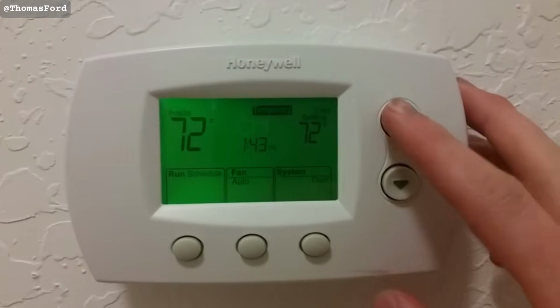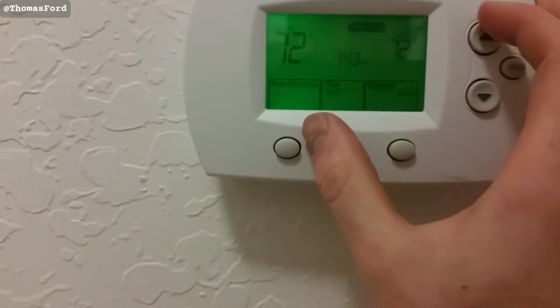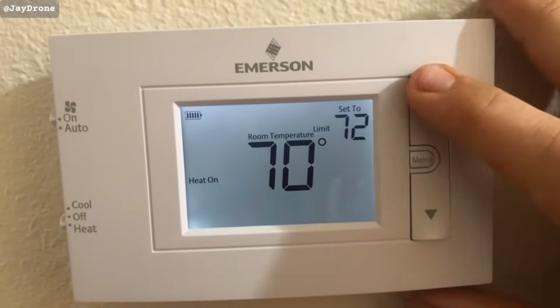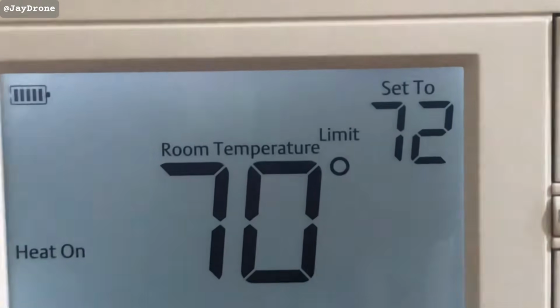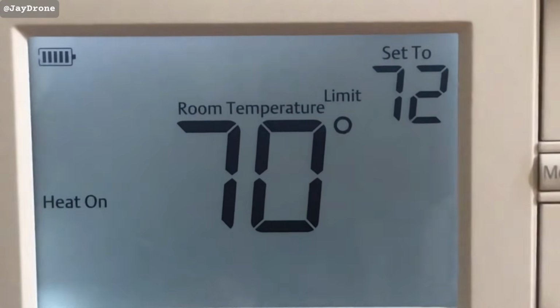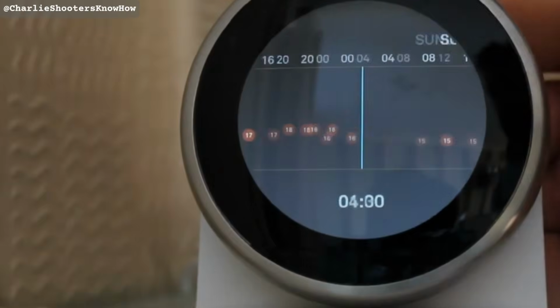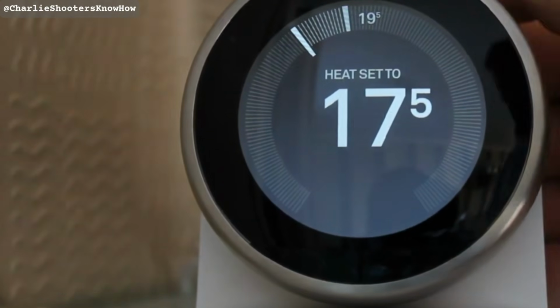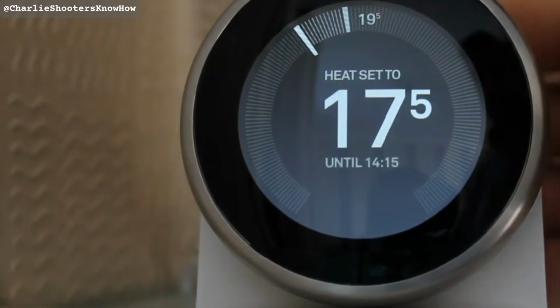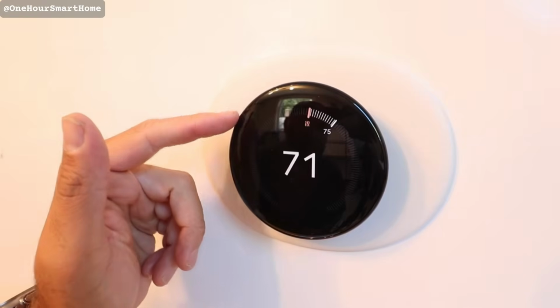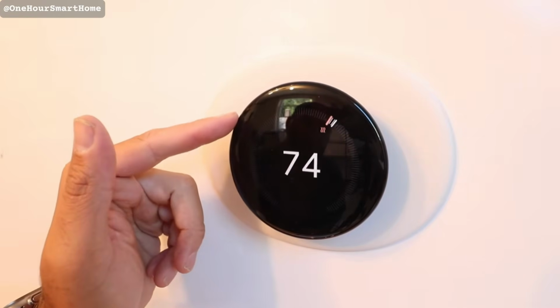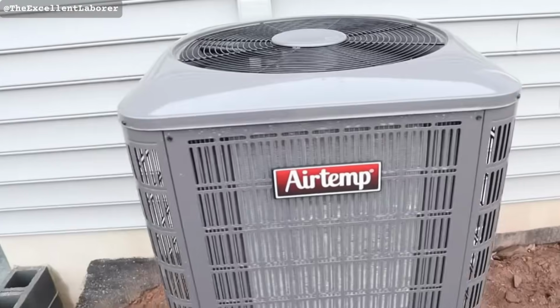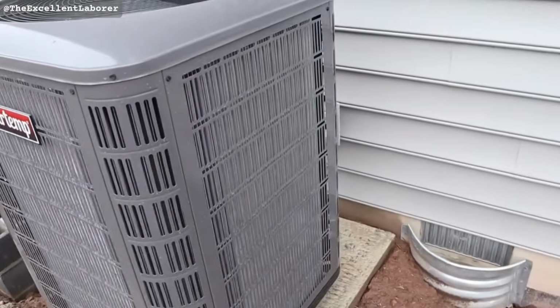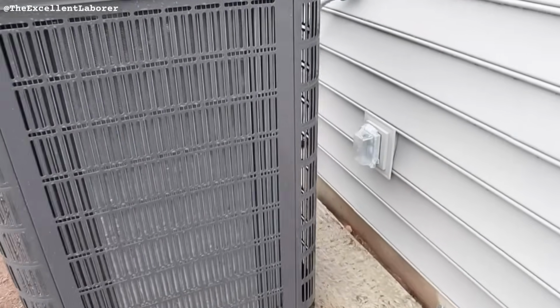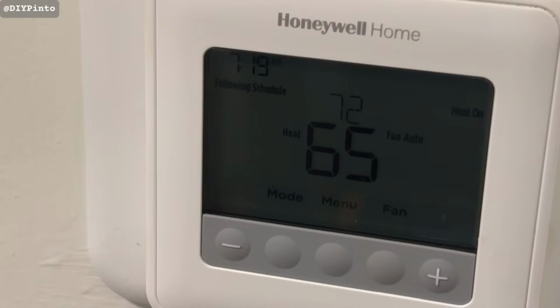The 5 strain sources I covered, electrical, airflow, thermal, refrigerant, cycling, each one adds up over decades. Address all 5 and your equipment stops failing the way most equipment fails. Address none of them and your system runs the same race every overworked, oversized, sun-baked, overfiltered unit in your neighborhood is running. The race ends with a contractor in your driveway quoting $9,000. The equipment doesn't have to fail. It mostly fails because we let it.